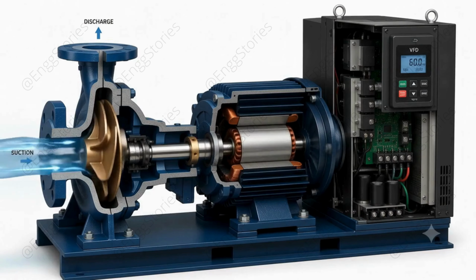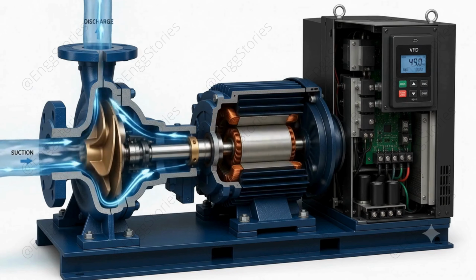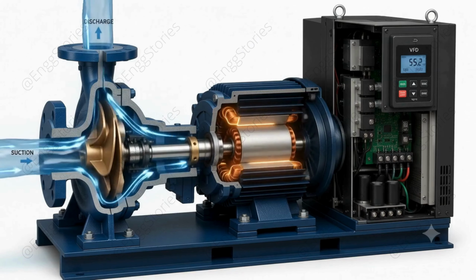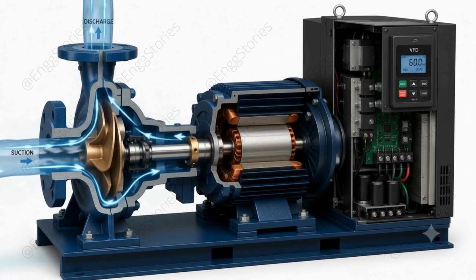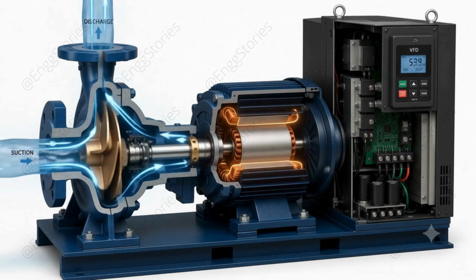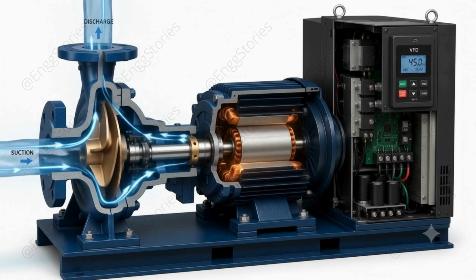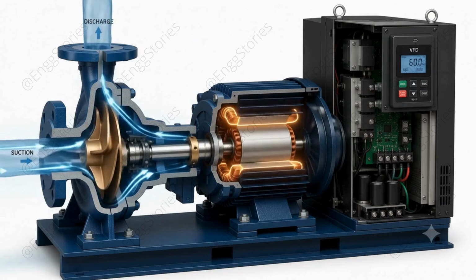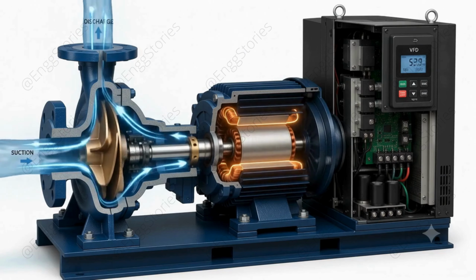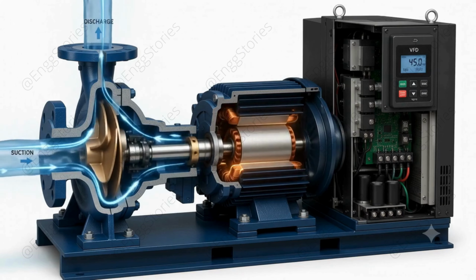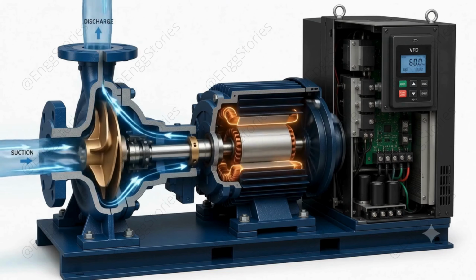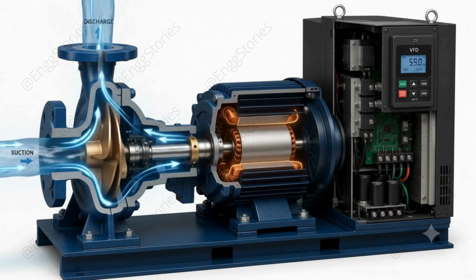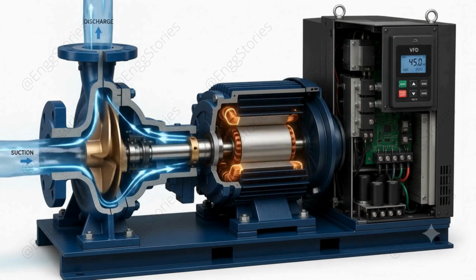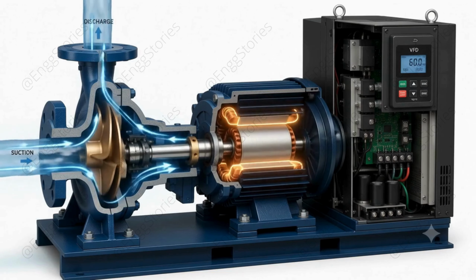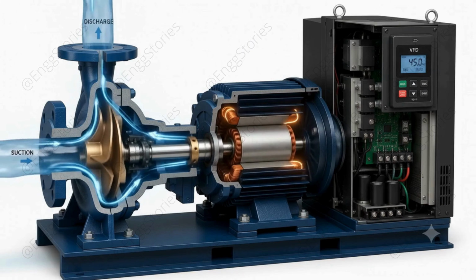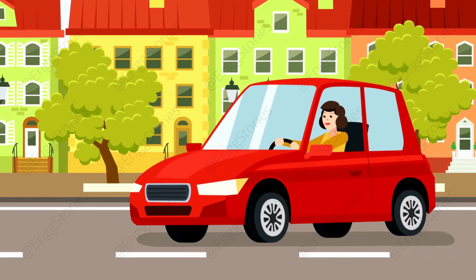In a water-cooled chiller system, we mainly use two centrifugal pumps, and each one has a different job. In modern HVAC systems, centrifugal pumps are usually equipped with a variable frequency drive, or VFD. Now, what is a VFD? VFD stands for Variable Frequency Drive. It is an electronic device that controls the speed of an electric motor by changing the frequency and voltage supplied to the motor. Think of it like the accelerator pedal in a car.